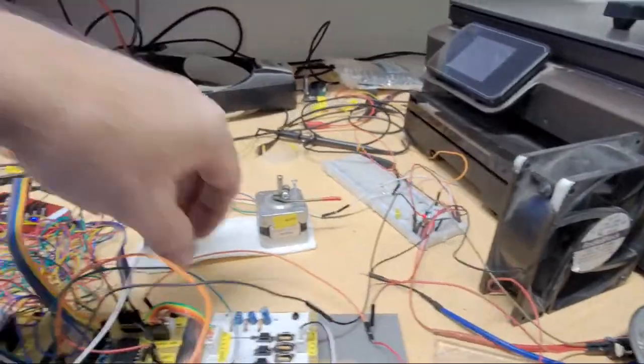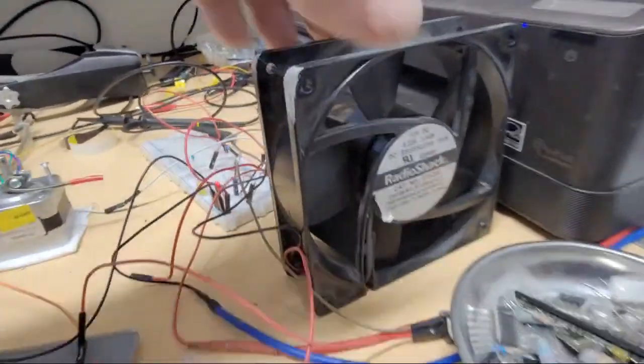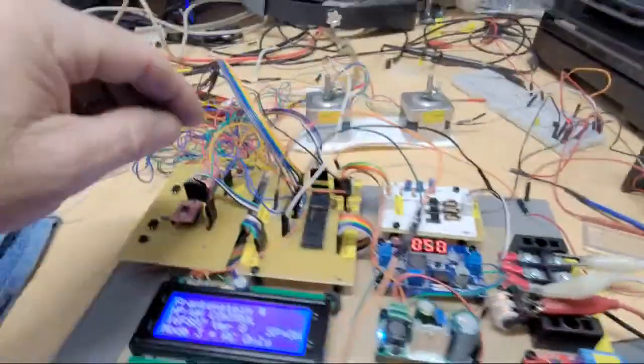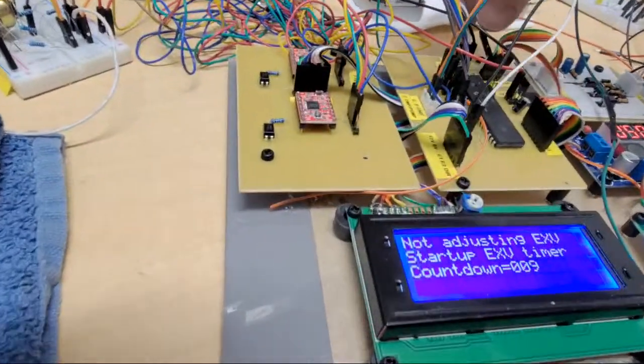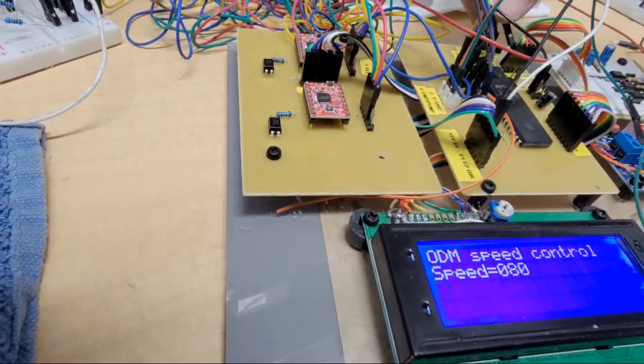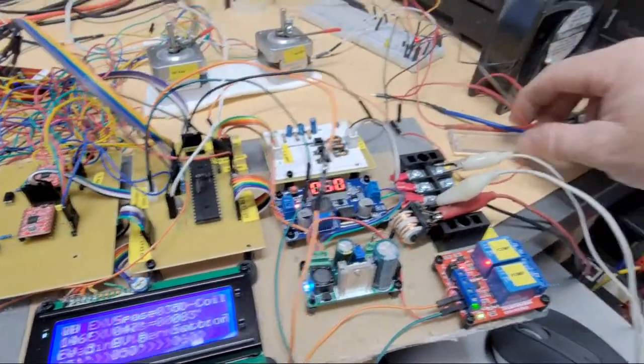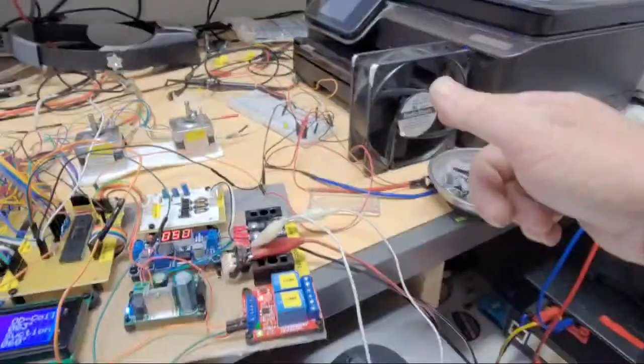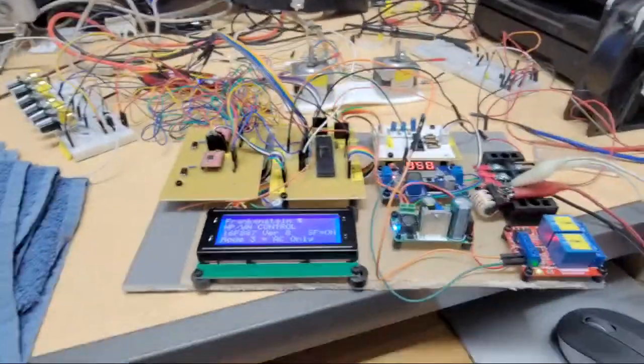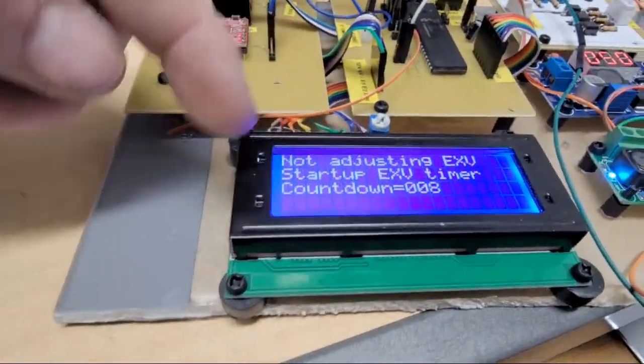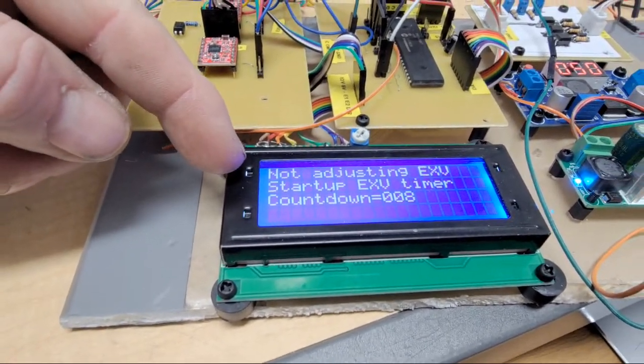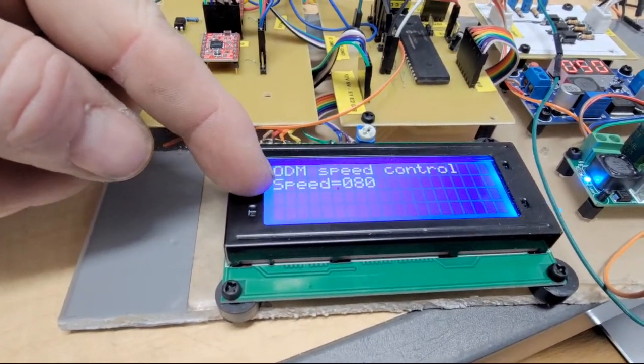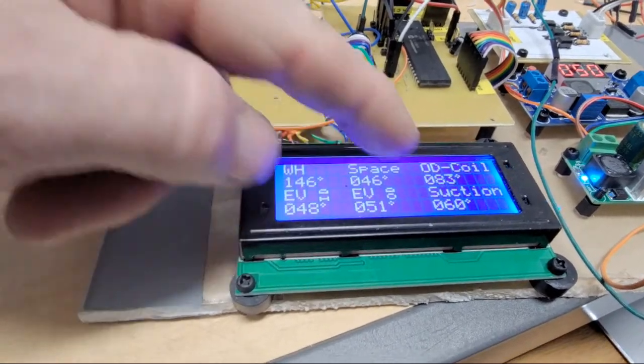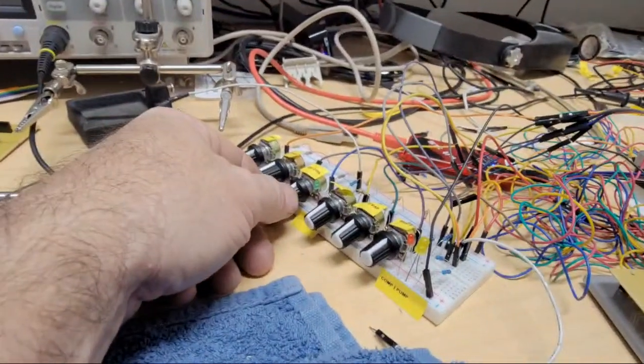It could be unhooked. I have stuff just kind of stuck in there. I could hear it want to run. I could have the pulse width too low. This stuff's been kind of kicked around, but I had that to simulate a condenser fan motor, and it would go around and basically had all those controls working. See, outdoor speed doesn't need to speed up because it's happy. It's right around 83.